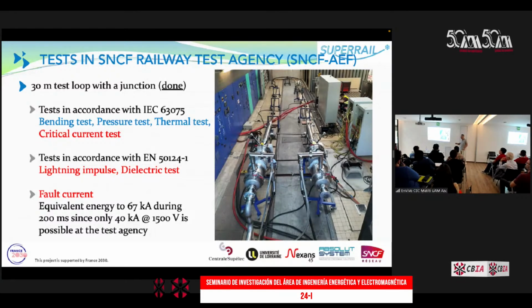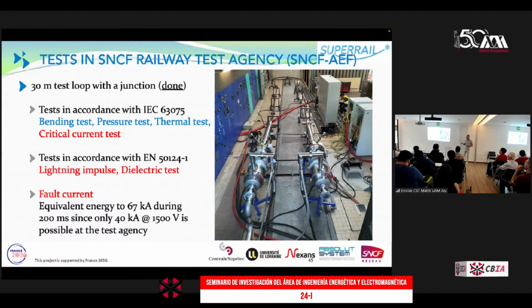First, we did some bending tests, because there are critical bending diameters for the cable. We also did pressure and thermal tests, because a huge elevation of temperature produces a lot of pressure, and you need to be sure the cable and all the security equipment will sustain a certain amount of pressure without breaking. In that case, I think it's 12 bar, at which point security equipment will open the system.